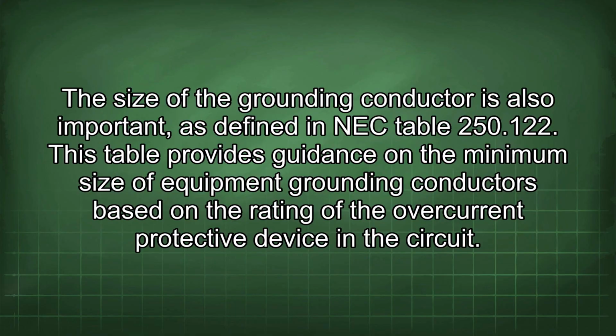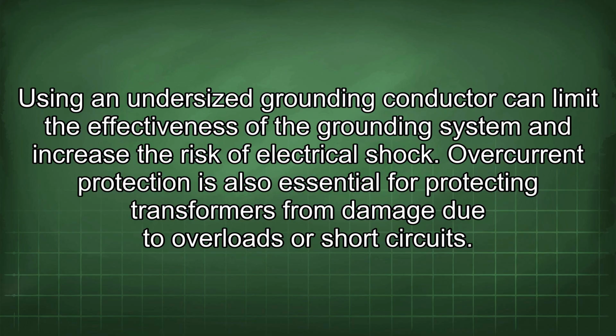The size of the grounding conductor is also important, as defined in NEC Table 250.122. This table provides guidance on the minimum size of equipment grounding conductors based on the rating of the overcurrent protective device in the circuit. Using an undersized grounding conductor can limit the effectiveness of the grounding system and increase the risk of electrical shock.